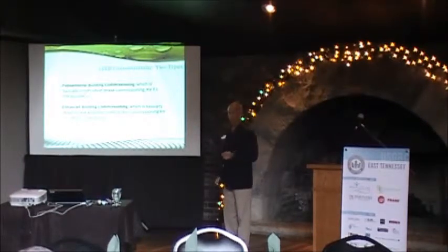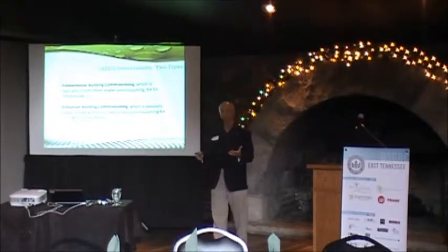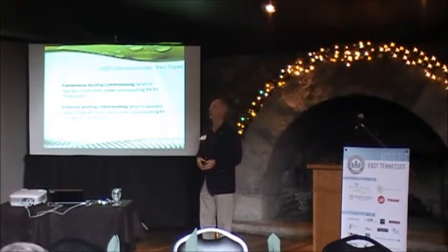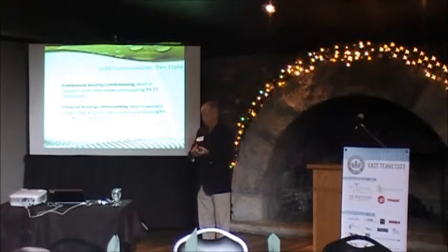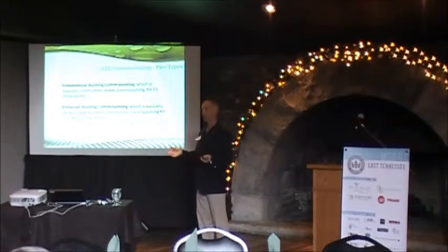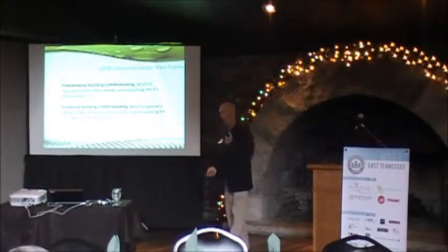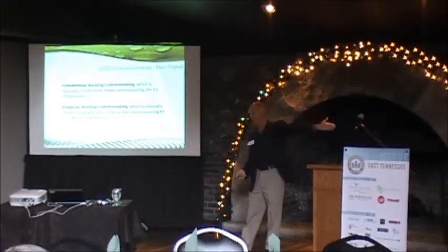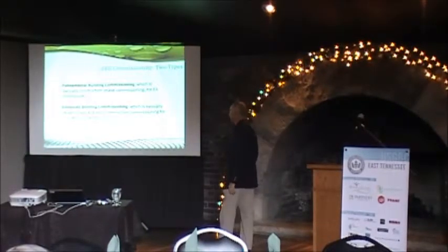There are two types of commissioning. Fundamental commissioning is basically construction phase, that's what you think of when you see the commissioning agent with the hard hat, clipboard, and digital camera walking around the building. That's what we were doing when we found the ductwork with the VAV unit that wouldn't open.